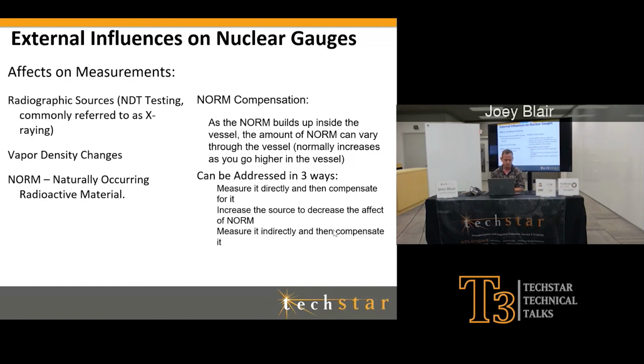Cody is asking, do Vega nuclear detectors work like a Vega radar when calibrating the false signal suppression? No. Okay, so they're completely different technologies. The similarity on those is going to be between. So the question was, in case you didn't hear Emily, is calibration on a Vega nuclear gauge going to be the same as a Vega radar gauge, or is the echo curve going to look the same? It's not. False signal suppression, none of that is there.